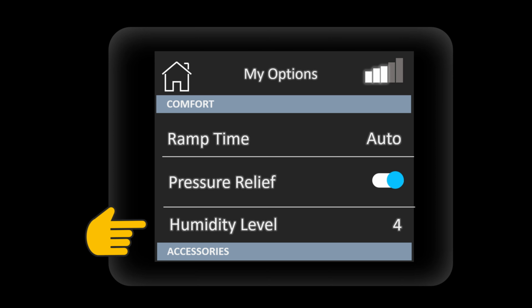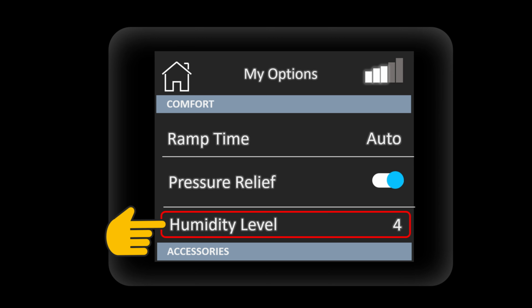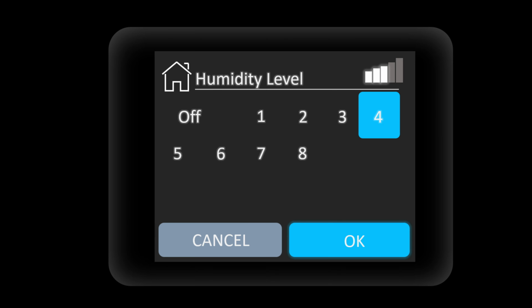Next menu that we're going to review is the humidity level. The humidity level controls the humidity output of your CPAP machine using heat. The default heat level is set at level 4. The higher the heat level, the warmer the air will get, which will result in more humidity. Every person has a different humidity preference, so it's good to start with the default heat level and adjust the level as needed. Once you have made your selection, tap OK to bring you back to the main menu.